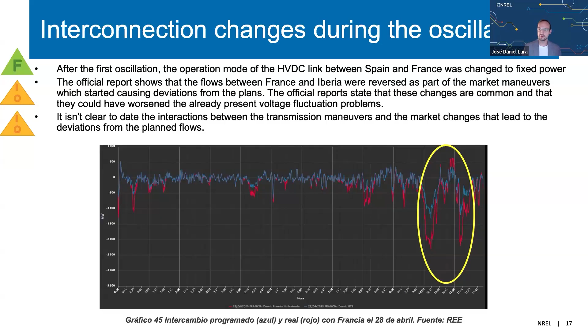This plot shows the interconnection changes, from data provided by the operator, and this is a far more detailed plot from the reports of Red Electrica, where you can see these reductions in the megawatt flows. What wasn't clear, and I think is still under study, is that we know the interactions between the transmission maneuvers done by the operator, but we don't understand if those also interacted with the market operations, because some of these maneuvers were happening while the market was changing and some units were coming online and going offline.